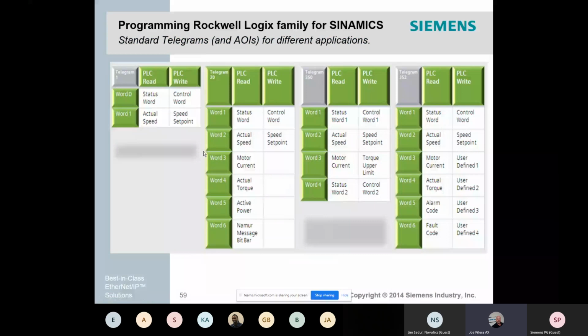Here we're showing the different telegram structures that are available, which are the standard telegram with the status word and a control word, the actual speed and speed set points. Using a telegram 20, we can get some additional feedback from the drive back to the PLC, given a status and control word and a speed set point. If your applications are more complicated, we can set up some torque limits and get some additional feedback. Here we can get alarm codes and fault codes as well.